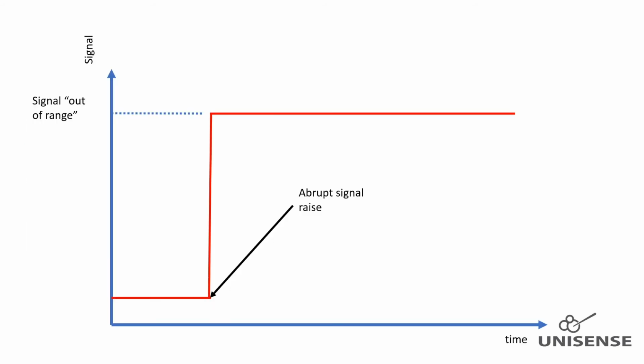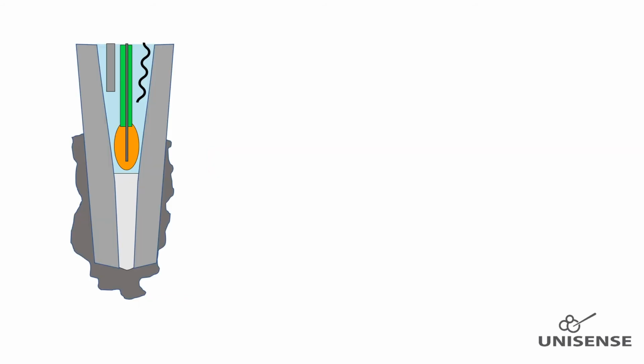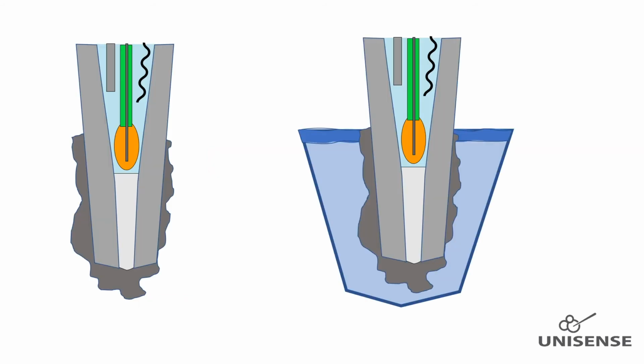If the sensor tip gets biofouled or covered with sticky polymers, it might measure incorrectly. The sensor tip tolerates almost all possible cleaning substances like alcohols, acid, detergents, proteinases, etc. So it is recommended to insert the sensor in different cleaning substances or solutions to see if this solves the problem as the first attempt to remove the fouling.